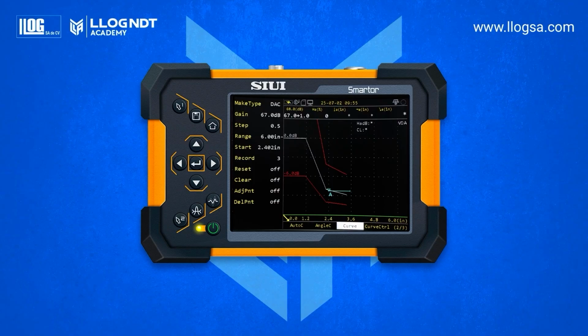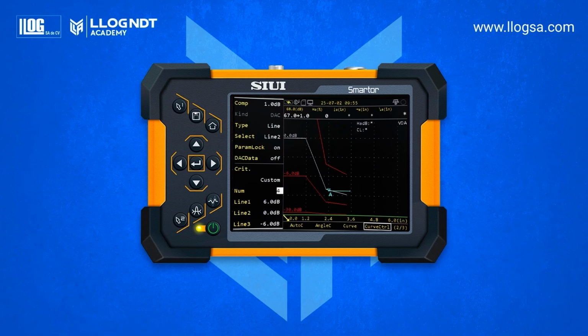Enter the Curve Control submenu. Two curves will be automatically generated, one at +6 decibels and another at -6 decibels, representing a discontinuity half the size of the reference level. We can draw up to 5 additional curves. For this example, we will add one at -14 decibels, representing a 20% sensitivity level. In the type function, we can also change the shape of the curves, either linear or curved.